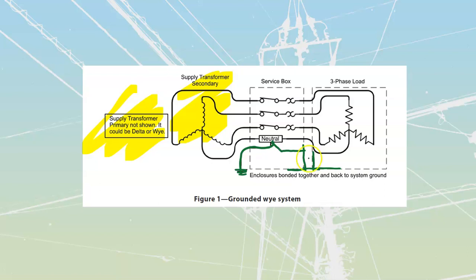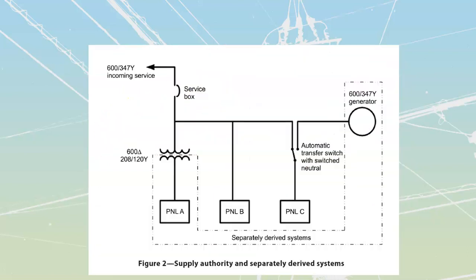There are 2 different types inside of your code of solidly grounded systems that we need to be aware of. Those are going to be what we refer to as our supply authority and our separately derived systems. CEC rule number 10-210 talks about our rules for solidly grounded systems supplied by the supply authority. And if I take a look at this, this would be a Y type of system, 600 volt, 347. Incoming Y, I see that that would feed into a service box, and then from the service box, I am sub-distributing out to a bunch of things. So I'm going down to this panel over here. I'm going up to this transformer winding over there, and I'm going over to this automatic transfer switch, which is then feeding down to panel C, where I might have emergency loads being fed out of.